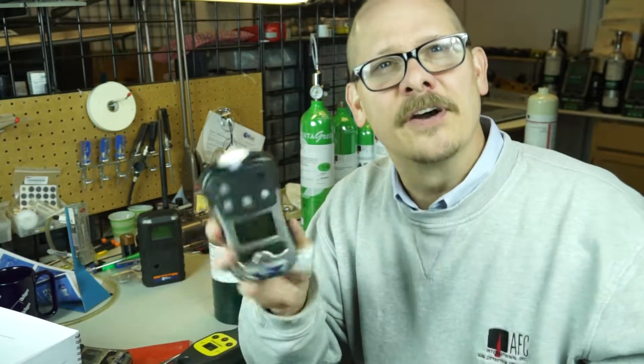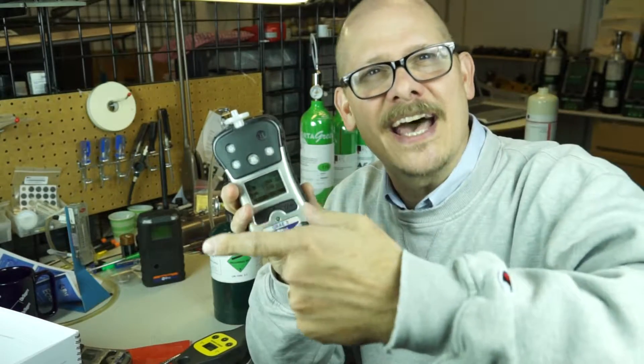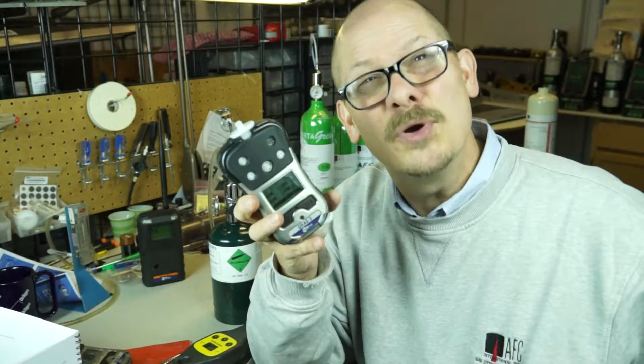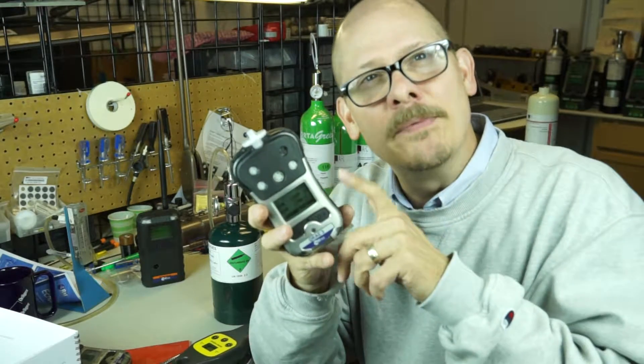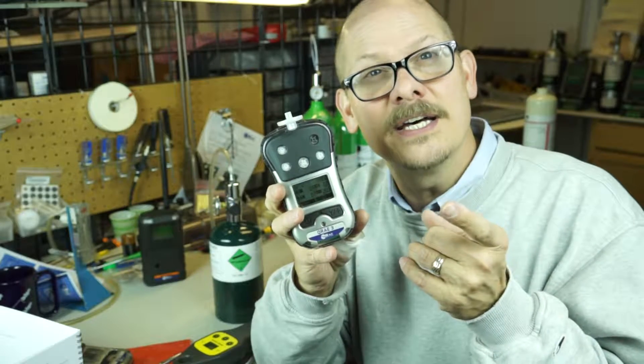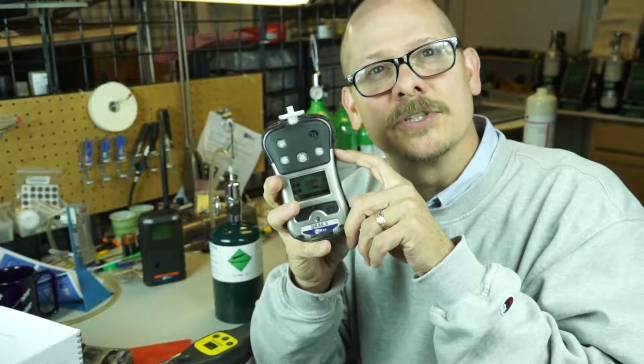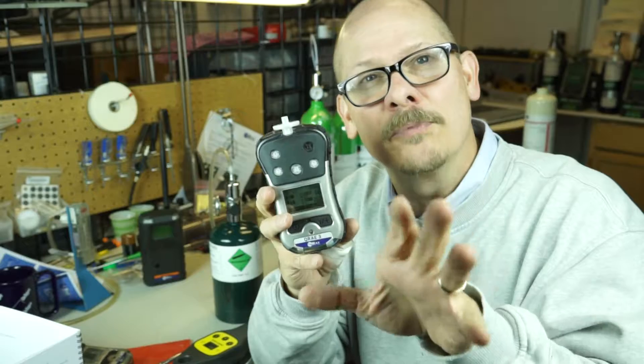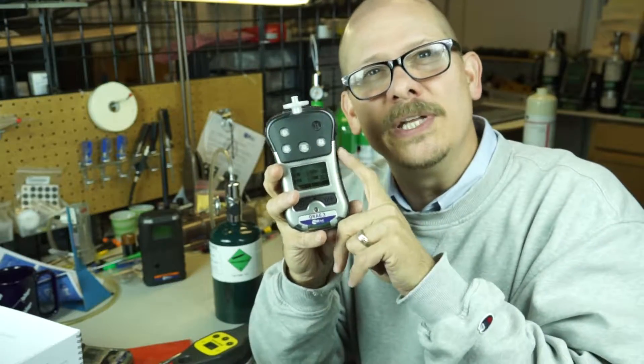So here's the problem. The fire department shows up at a house and the homeowner, the dog, the gas guy — everybody says 'I smell gas.' You smell the gas because you can smell it at 0.01, 1, or 2 parts per million. But the problem is the instrument the fire department just brought in can't see it because it's too low — lower than the detection limit of their LEL sensor. Remember, 1% LEL is 500 parts per million. We're smelling it at 1 or 2, but our meter only starts reading it at 500.